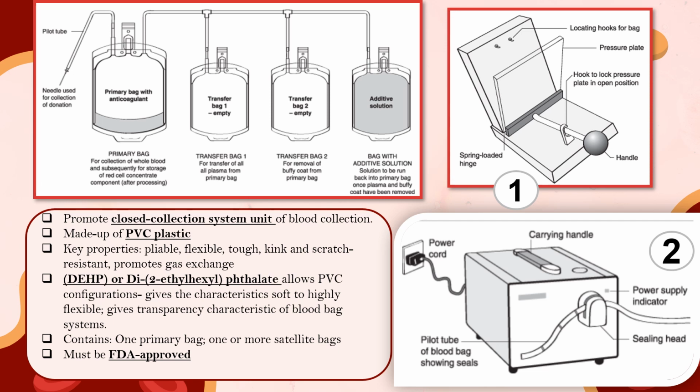Your DEHP, or di-2-ethylhexyl phthalate, allows PVC configurations, which give the blood bag soft to highly flexible characteristics. And this also gives the transparency characteristic of the blood bag system. So if you have encountered blood bags before, you can notice that they are nearly transparent or translucent.